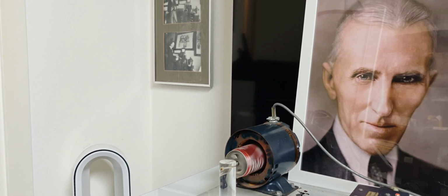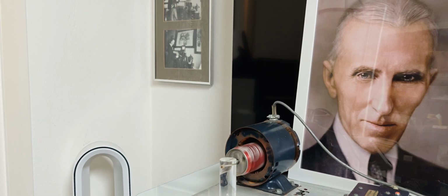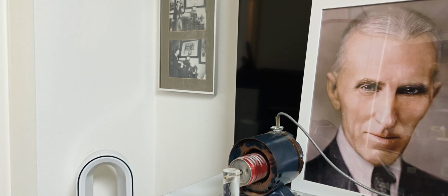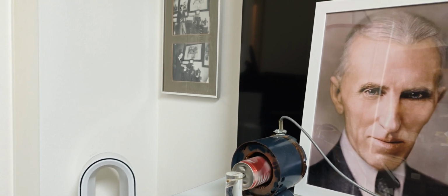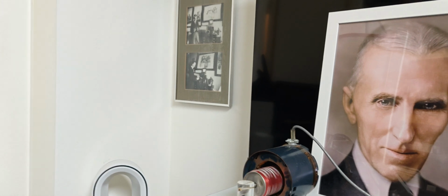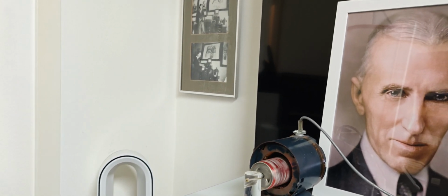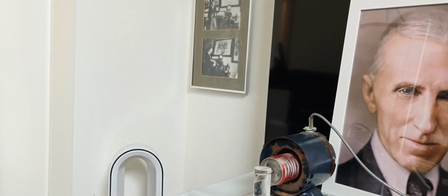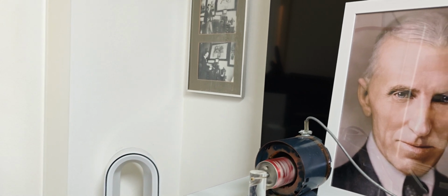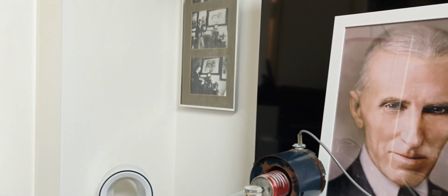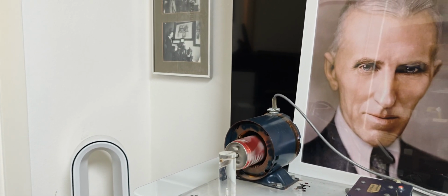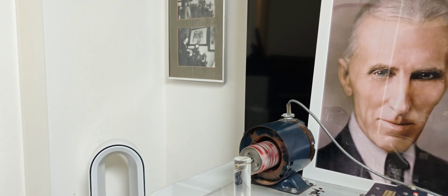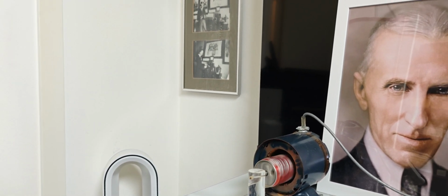There is from 3 stator windings, or 2 stator windings in this case, a 2-phase motor. You create a rotating magnetic field, and the rotating magnetic field miraculously creates in the secondary, which is short circuited, also a rotating magnetic field, which actually is pushed by the primary with a little lag, which is called a slip. That's why an induction motor could never reach the synchronous speed of 3,600 RPM, but it's coming close to 3,500, and this difference is called a slip.